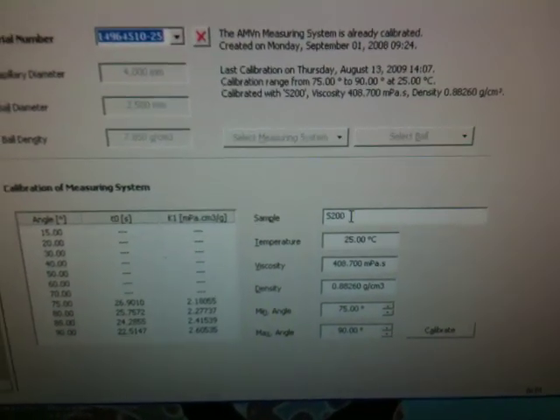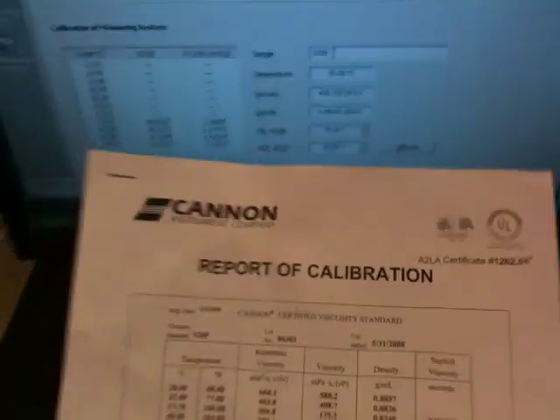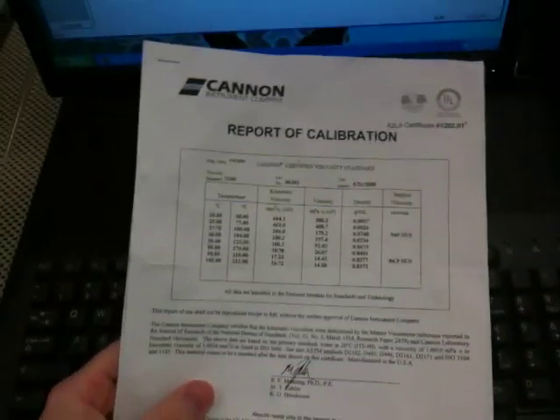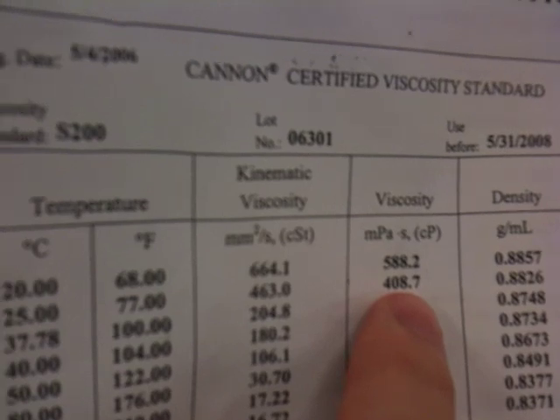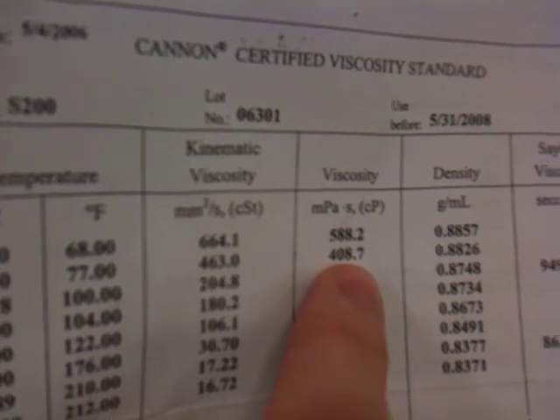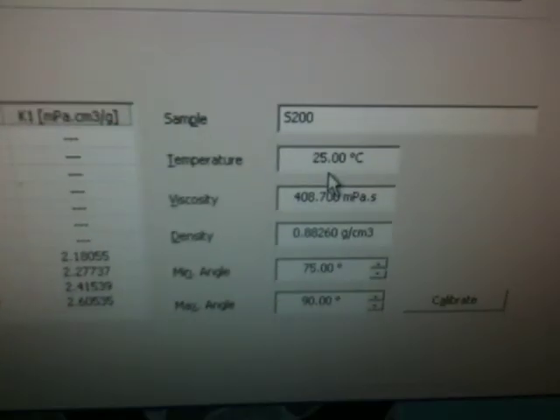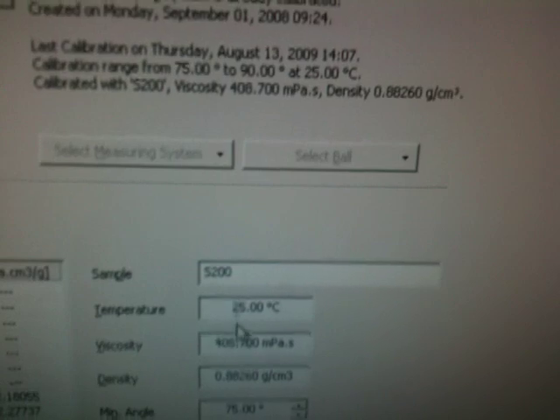Now for this one, we use the S200. This one's already been calibrated. And we went to this sheet right here, and we looked at 25 degrees. The dynamic viscosity should be 408.7. And make sure your units are the same. And this is the density. You enter the temperature, the name, and the viscosity, and the corresponding density.